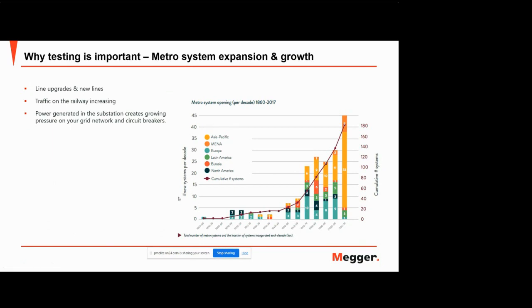So we have the power generated in the substation now, because there's an excessive amount of power generation to cope with the increasing passenger demand. That also adds pressure to your grid network, but it also adds pressure to your protection scheme from your relay all the way down to your circuit breakers. So that's another very important reason to continue to test your protection scheme, to make sure that it's working to specification with the increasing demand on your DC network.